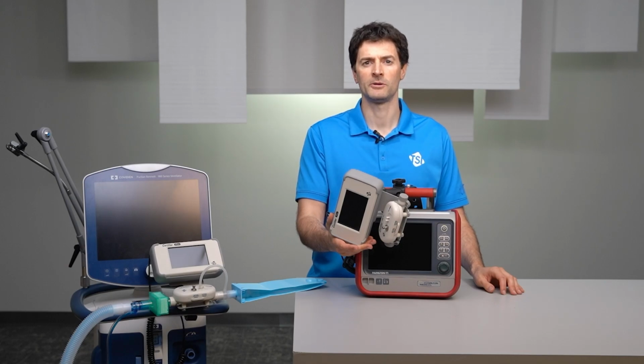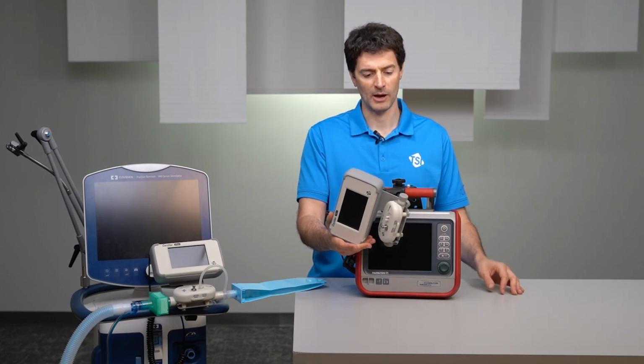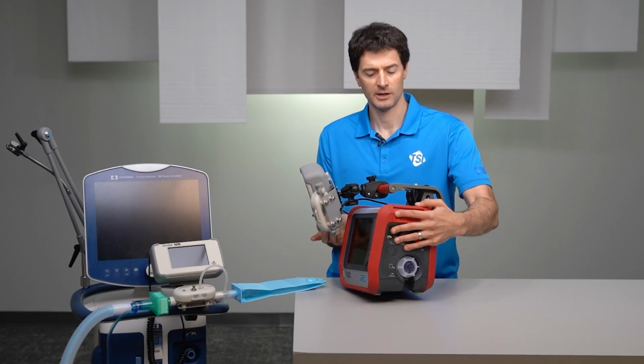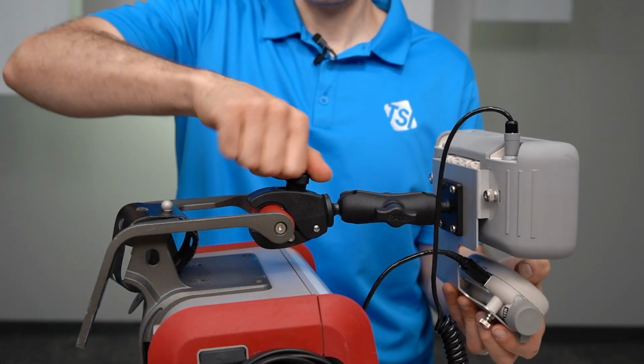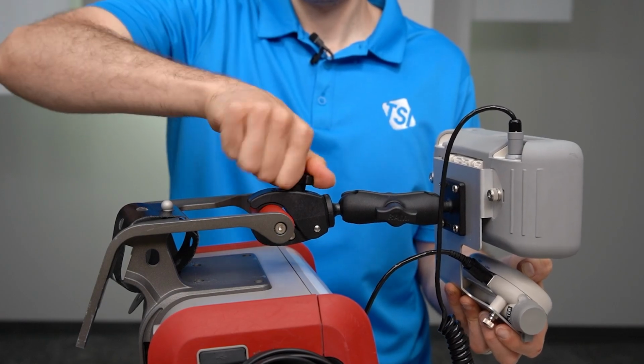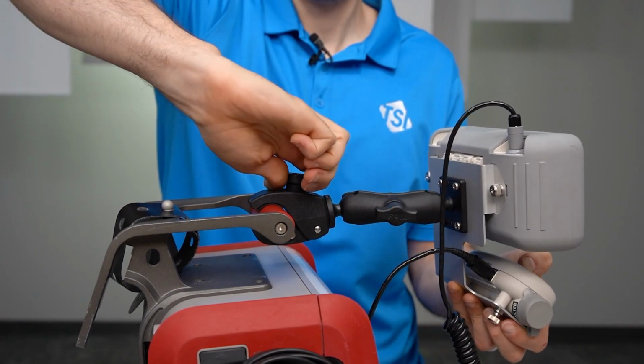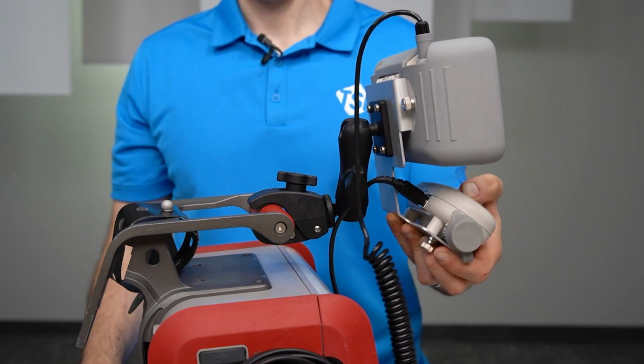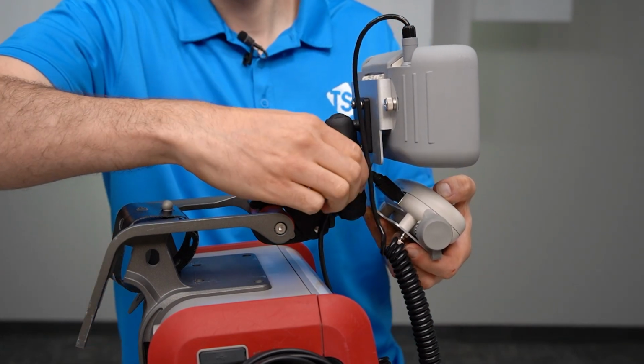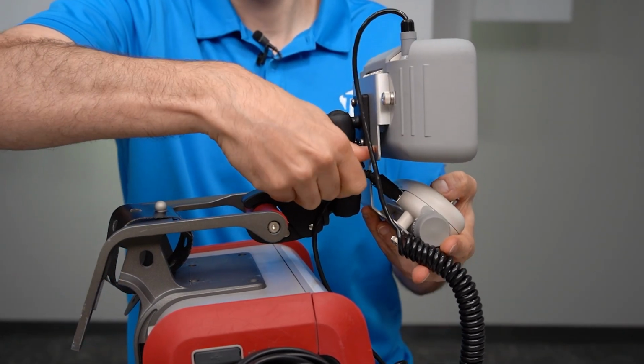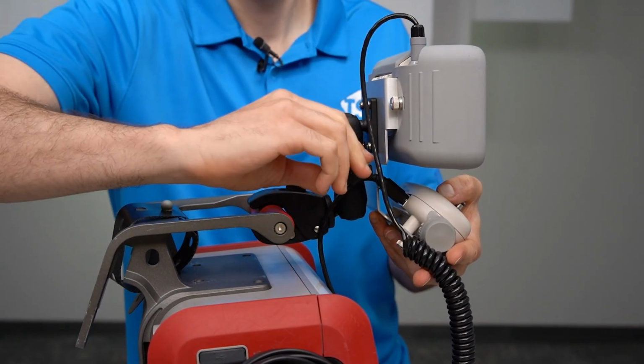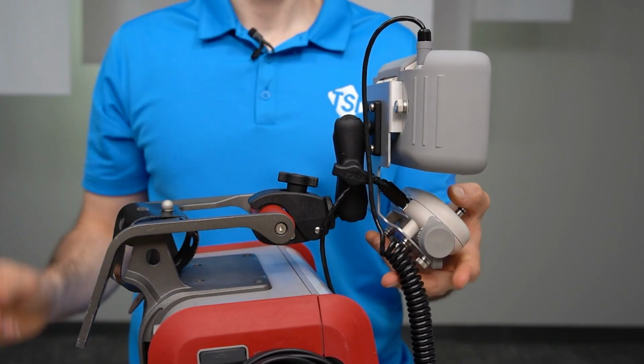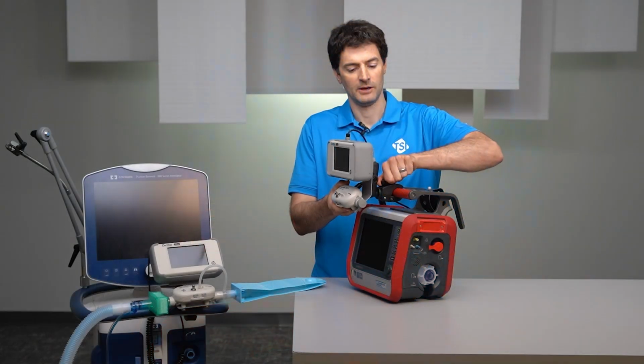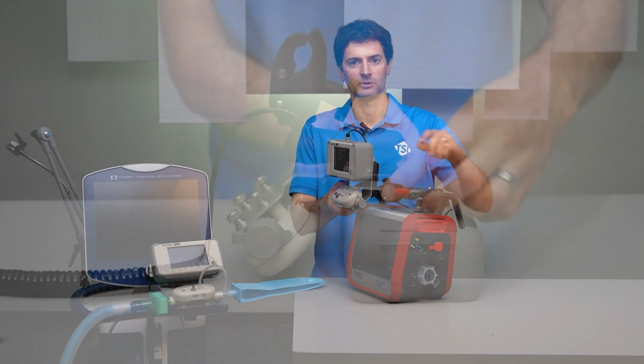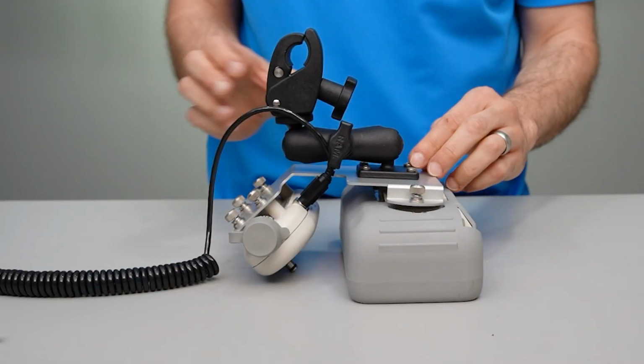Once your certifier modules are connected to the mount, clamp the assembled mount onto the ventilator rail and then adjust the double jointed arm to optimize the positioning of your certifier for testing. When your testing is completed, remove the mounted certifier from the ventilator rail and disconnect the flow modules from the adapter plate.